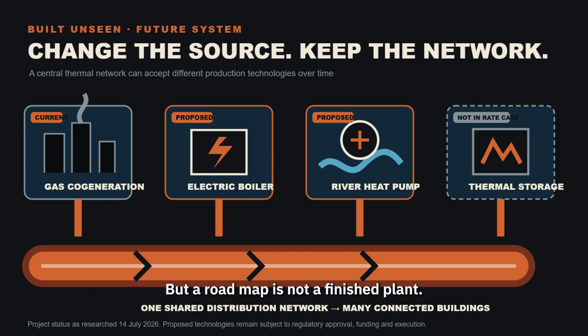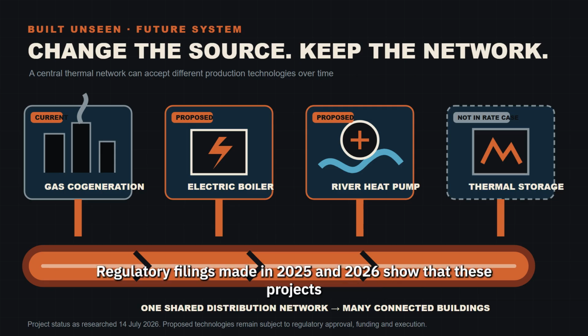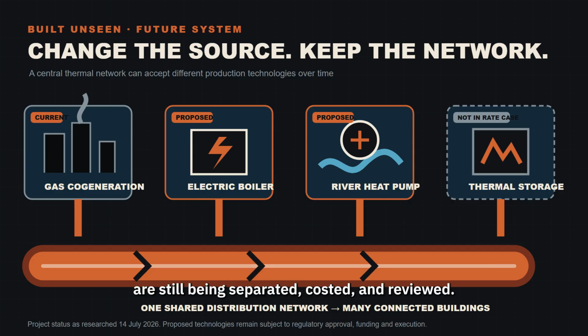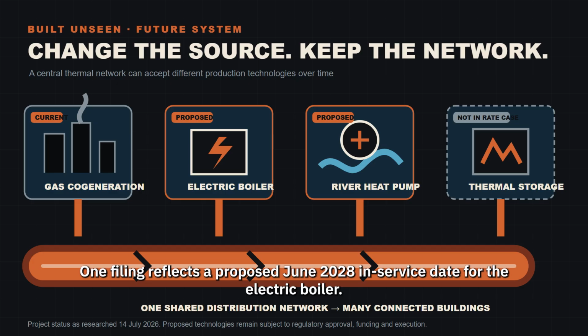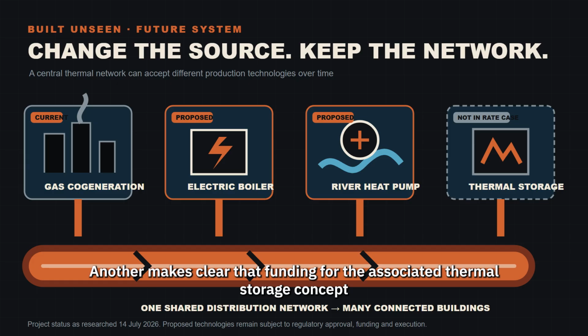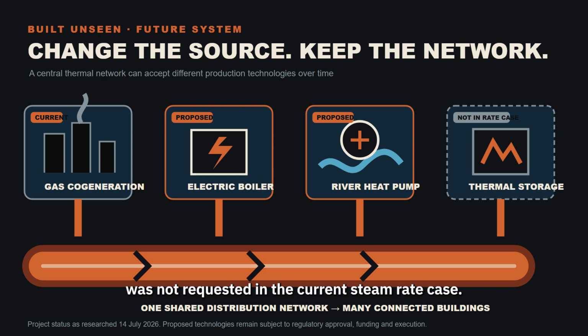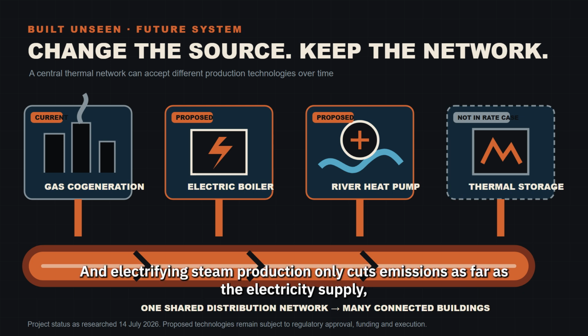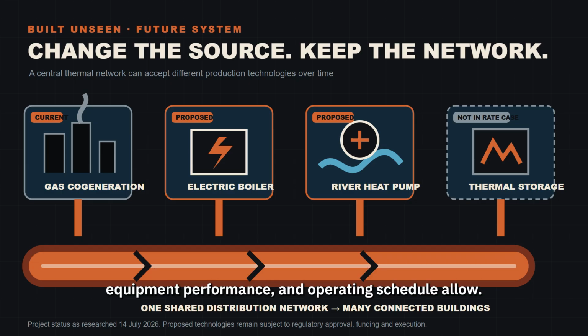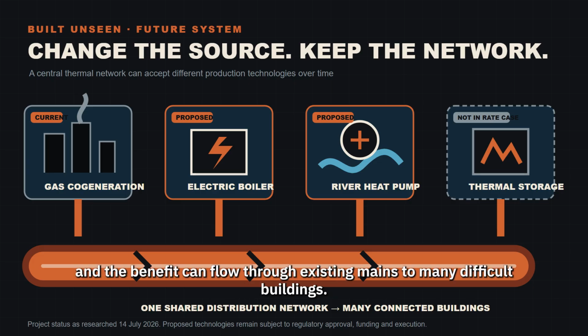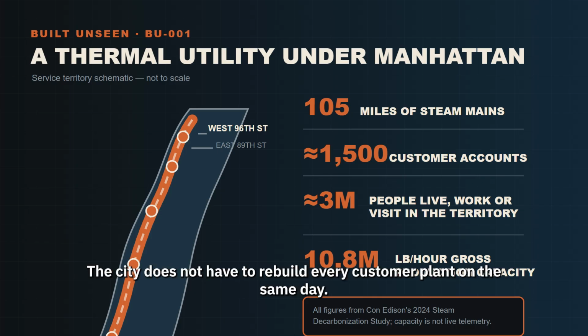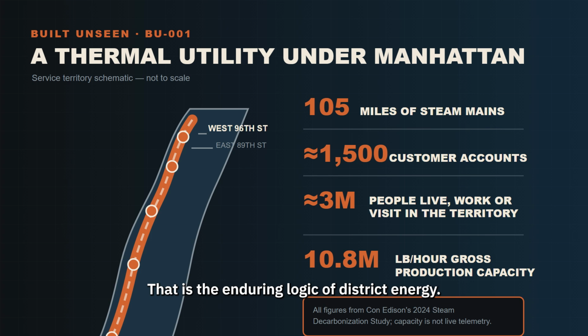But a roadmap is not a finished plant. Regulatory filings made in 2025 and 2026 show that these projects are still being separated, costed, and reviewed. One filing reflects a proposed June 2028 in-service date for the electric boiler. Another makes clear that funding for the associated thermal storage concept was not requested in the current steam rate case. And electrifying steam production only cuts emissions as far as the electricity supply, equipment performance, and operating schedule allow. The opportunity is nevertheless significant. Upgrade one central source, and the benefit can flow through existing mains to many difficult buildings. The city does not have to rebuild every customer plant on the same day. That is the enduring logic of district energy. A network can outlive the technology that first fed it.